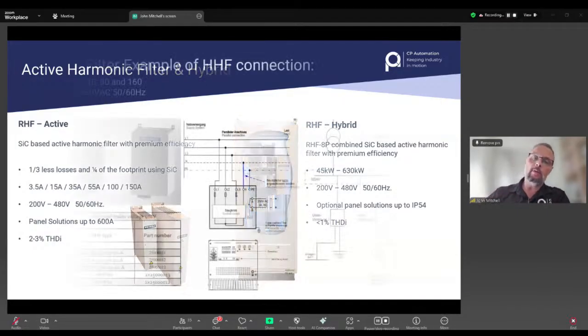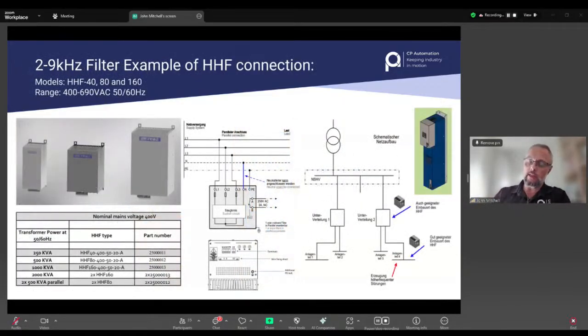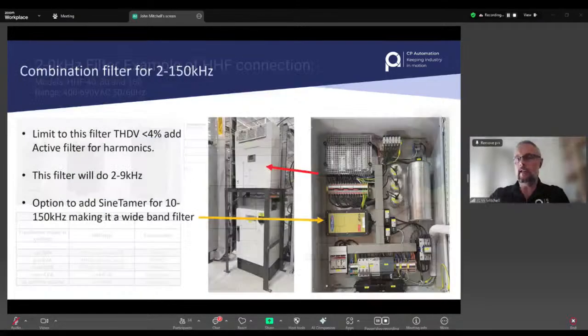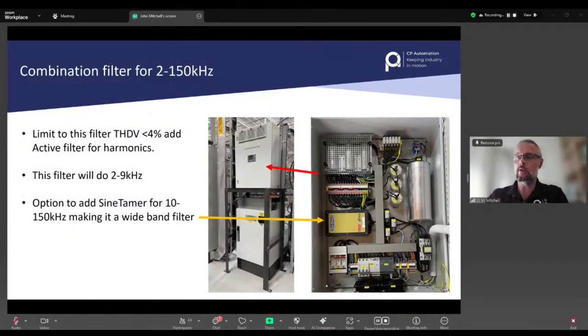Then into super harmonics, as I mentioned in that section, it's broken into two areas: 2 to 9 kilohertz and 9 to 150. For the 2 to 9 range, we have this product, and then for light industrial applications like shopping malls, we have this other product. In addition, we fit the sine tamer that you can see in the panel, which removes the higher frequencies. So we can do a really wideband filter solution for your customers.